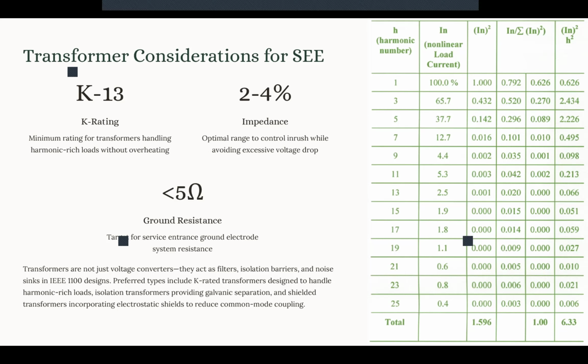All the transformers should have a grounding resistance. When we talk about the IEEE 1100, the limit is less than 5 ohm. This limit is for the service entrance ground electrode system. Okay, this 5 ohm, please don't get it confused with that 1 ohm criteria that we mentioned. That 1 ohm criteria is for the SRG, the signal reference grid. This 5 ohm is for the service entrance ground, because the transformer is at the entrance of our power distribution. Now, these are the recommended criteria from the IEEE 1100 for the transformer that we use in our power distribution system.